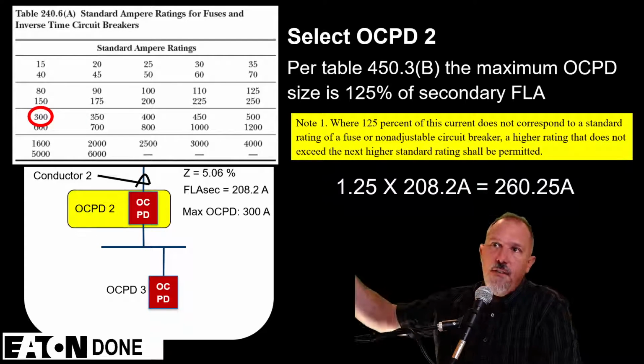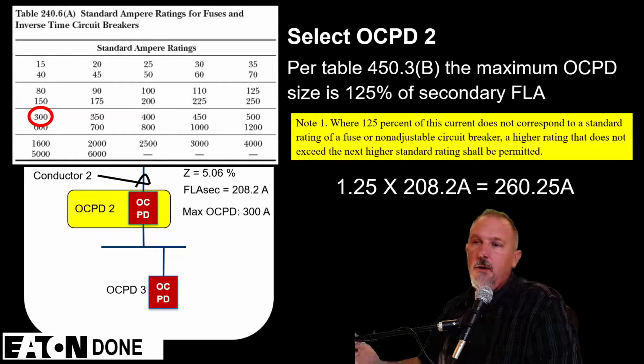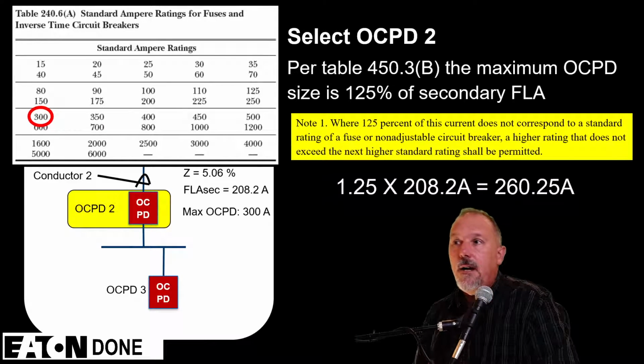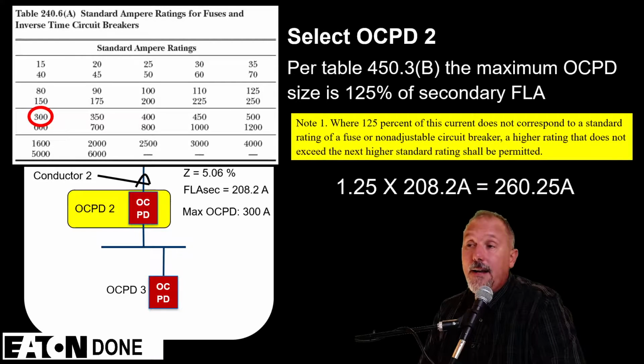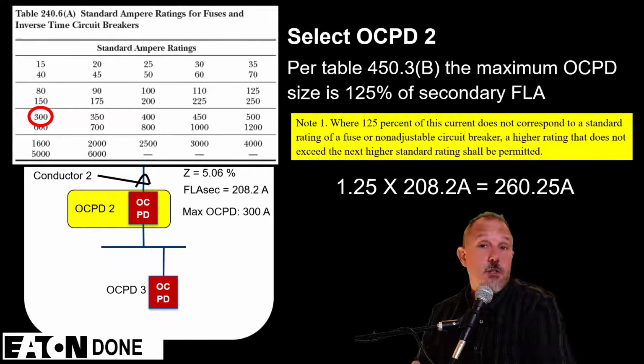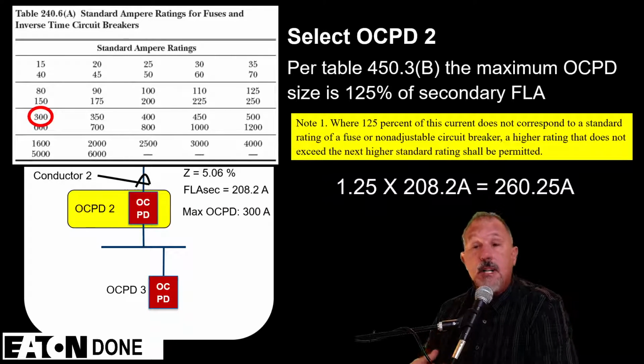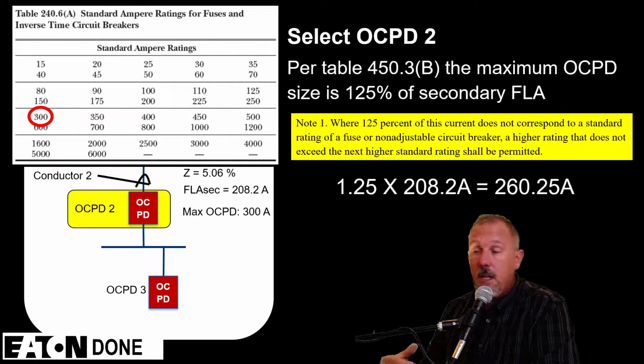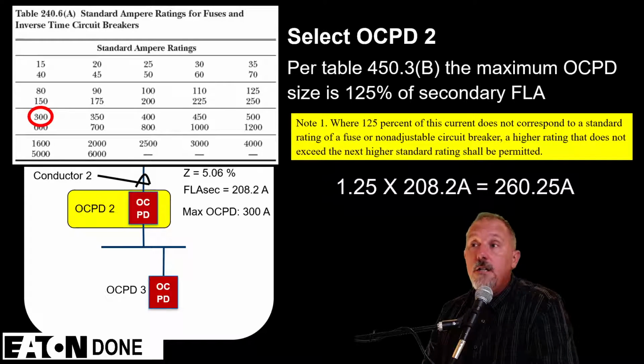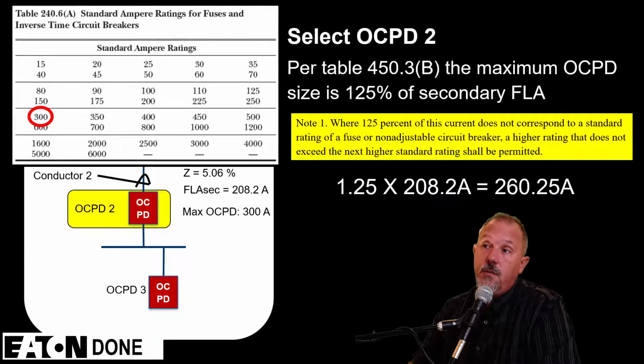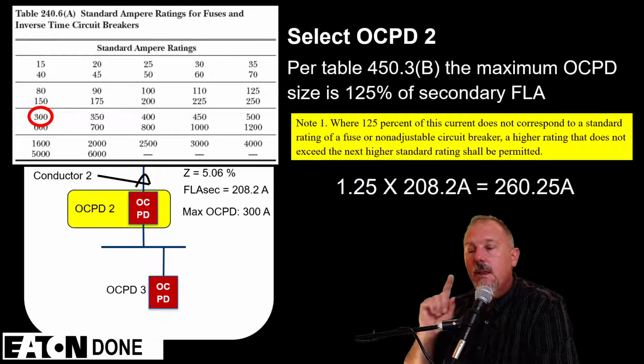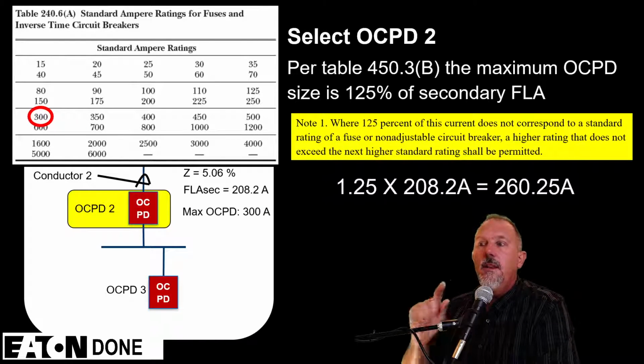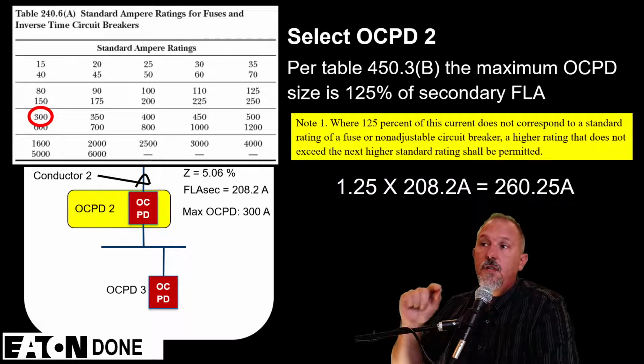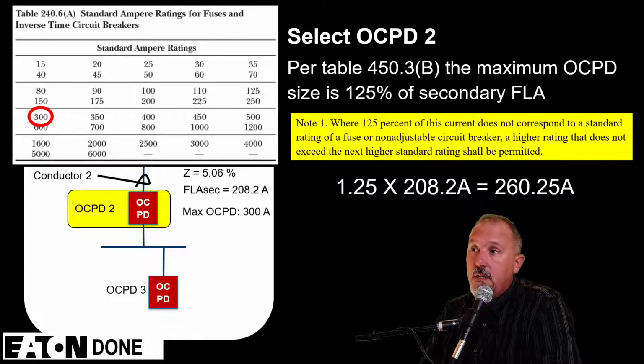So if I put a 250 amp primary breaker on and I put a 300 amp panel board with a 300 amp main, I could load this puppy up. There's nothing in the National Electrical Code that tells me I have to size my transformer to the load. So I could take this transformer and really push it hard, which would add to the heating and could possibly reduce the life of that transformer, but I would still be following the National Electrical Code minimum requirements for safety if I used a 300 amp panel board on this application.